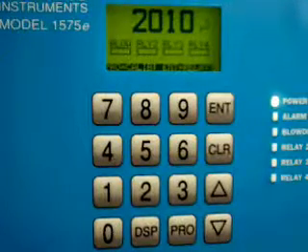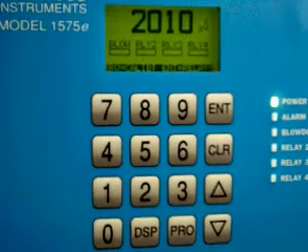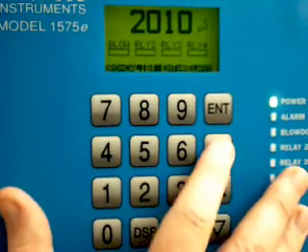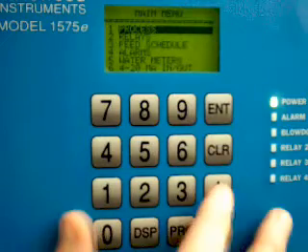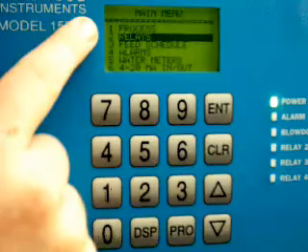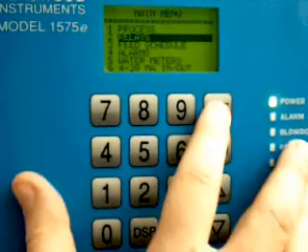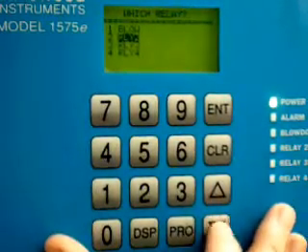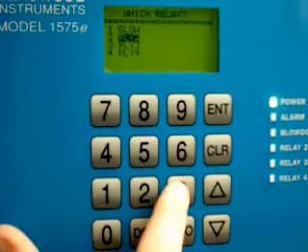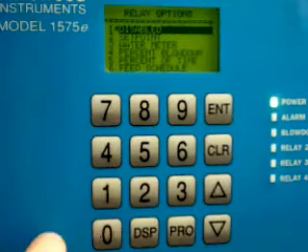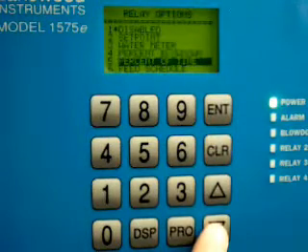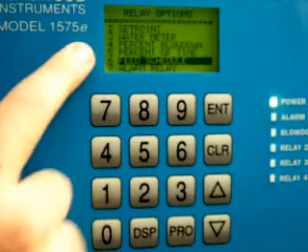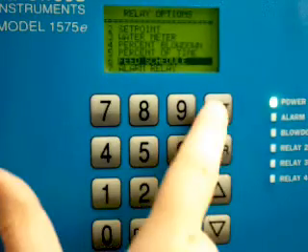To program a relay, we're going to program relay three to be used as a biocide feed. First, I hit clear, and then I scroll down to relays. So in English, I want to mess with a relay, I go to a relay. Press enter. Scroll down to relay three, or I could just push relay three, the number three on the keypad. Now this is currently disabled.